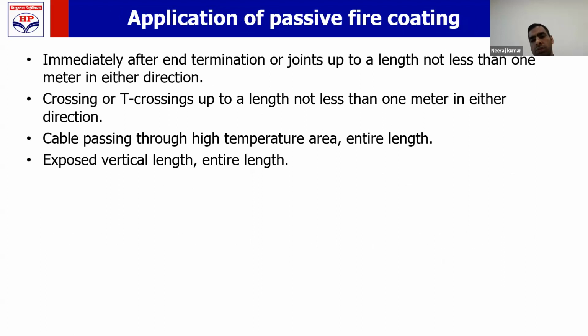Many times you must have seen that fire retardant coating, which is also called passive fire coating, is done on the cables. Now, where it should be done, where it should not be done. The passive fire coating or fire retardant coating shall be done immediately after end termination of the cable, or at the joints up to a length of 1 meter on each side. जहां आपका joint है 1 meter this side, 1 meter that side. At the crossing of the cable or T-crossing of the cables, 1 meter on each side.